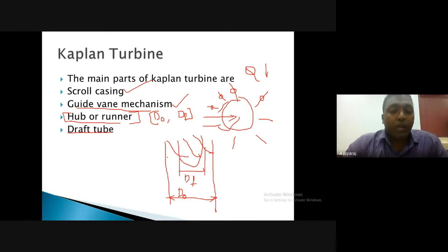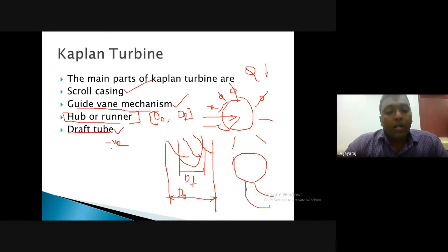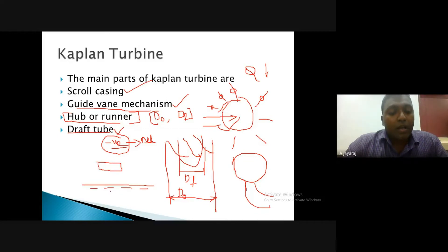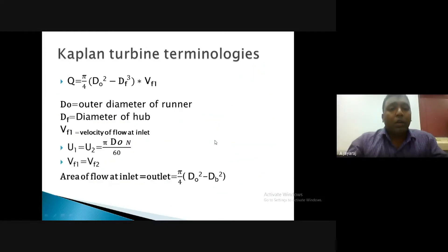The draft tube is another important component. It enables a negative pressure at the exit of the turbine, leading to an increase in net pressure. It also ensures that the turbine can be installed at a greater height compared to the tail race. The draft tube serves two main purposes: maintaining negative pressure at the turbine exit and allowing the turbine to be positioned at a sufficient height above the tail race level.